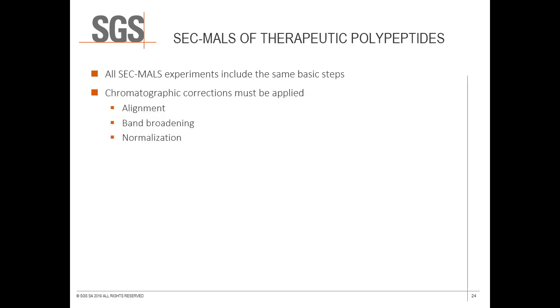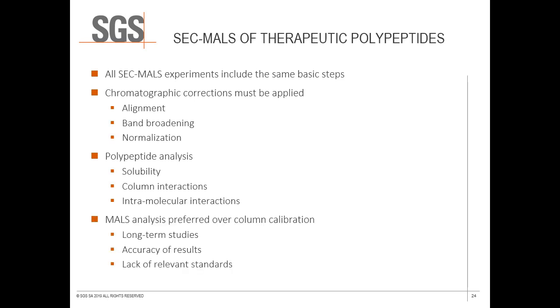In review, all SEC-MALS experiments have the same basic steps of dissolution, injection, separation, detection, and results calculation. Detector signals must be aligned and corrected for band broadening using a narrow standard, and light scattering detector angle voltages must be normalized using an isotropic scatterer. Polypeptides can pose particular challenges for solubility and preventing column interactions. Be sure to check chromatographic data for evidence of column interactions in the form of severe peak tailing. MALS analysis is typically preferred over column calibration due to long-term reproducibility and the accuracy of molar mass results, as well as the lack of relevant standards for samples such as polypeptides.